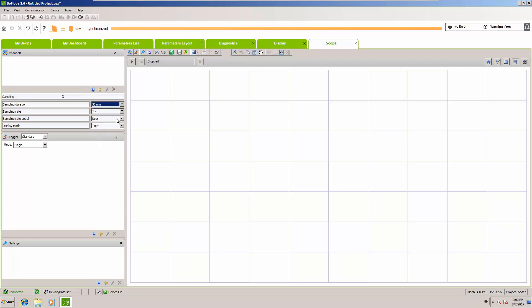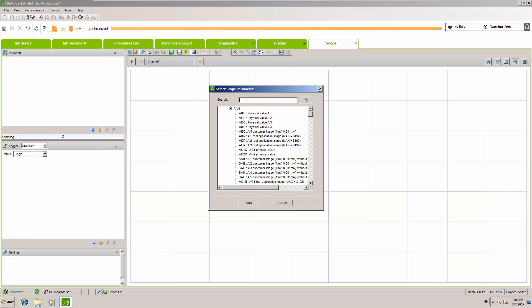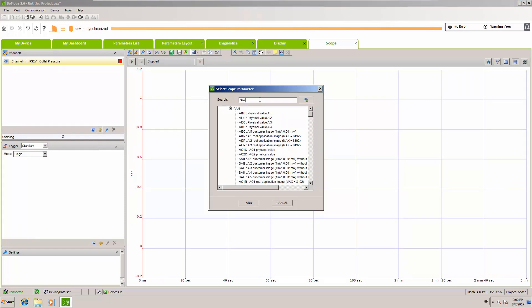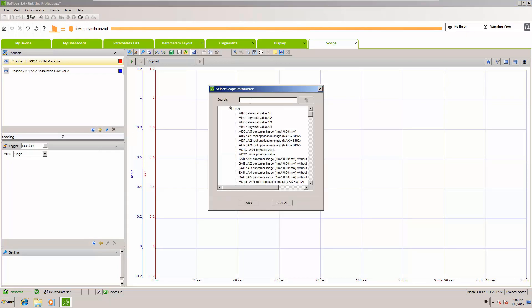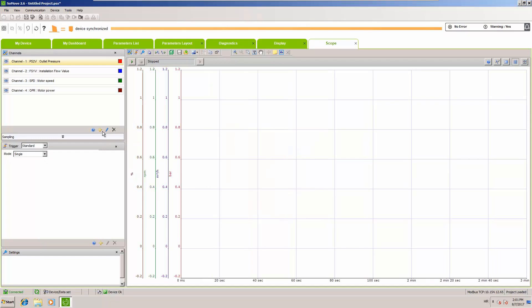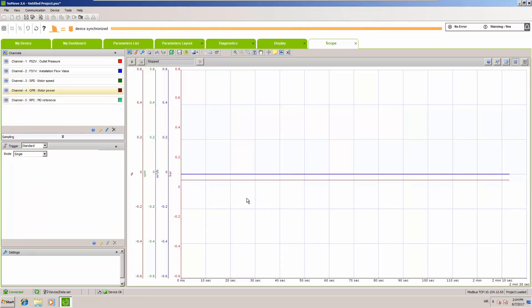For the values to follow in the scope: first, outlet pressure — interesting to see how pressure is maintained. Then installation flow — to compare pressure against flow. Then motor speed, to see correlation. And finally motor power, which I will explain at the end as it can be interesting. Additionally, we follow PID reference just to confirm our PID is working correctly. Once the scope is set up, we can run it and go to our practical demonstration.